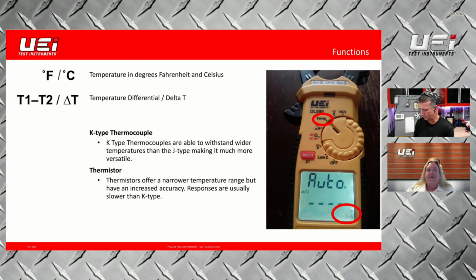I can do temperature differential as well. So if I'm reading a temperature split across an evaporator, I can utilize both probes and get the difference of temperatures.